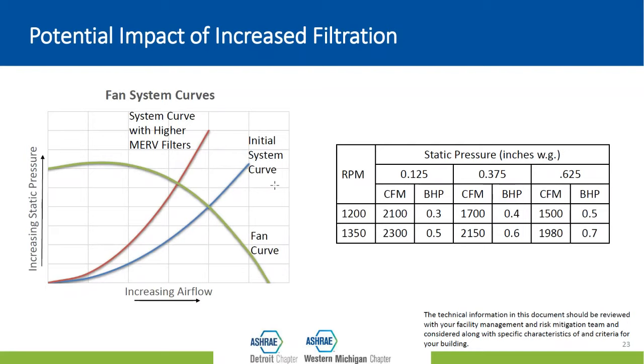Now, when the filter gets a little dirty, it's going to slide up on that fan curve a bit, as much as, you know, a half an inch or what have you. It typically tends to double the starting pressure drop. If you increase to a higher MERV level, it's going to move further up on that fan curve. And you can see here the red, where the red curve hits that fan curve, you're moving significantly less air through the system, which means you may not get as much airflow as you need to the spaces in your building. Right, you may be reducing airflow to the building by increasing the filtration level. So this is something that you want to have your facility team definitely take a look at and give consideration to before you just make a carte blanche change to increase the MERV value of your filters.